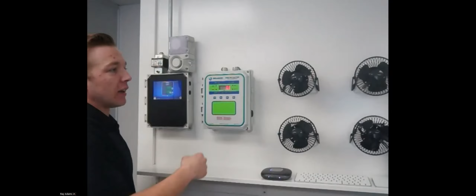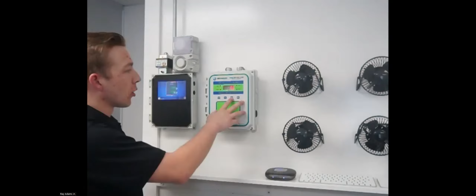So as you can see on our display fixture here, we have a first fan and a second fan that are configured on our standalone unit. Now, you can activate those by the sensors detecting gas. You can also use a manual override that you can hit to turn those fans on within the facility. But generally, the gas hits a certain level. For us, our factory defaults for carbon monoxide are 35 for the low alert and 100 parts per million on the high alert. So you would see that first fan kick on when your gas level is above 35. If that were to continue to rise and reach above 100, that's when your secondary fan would kick on.